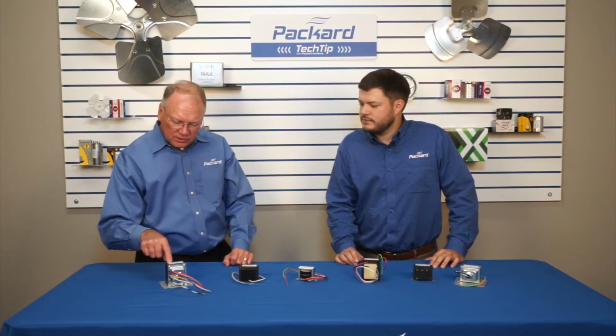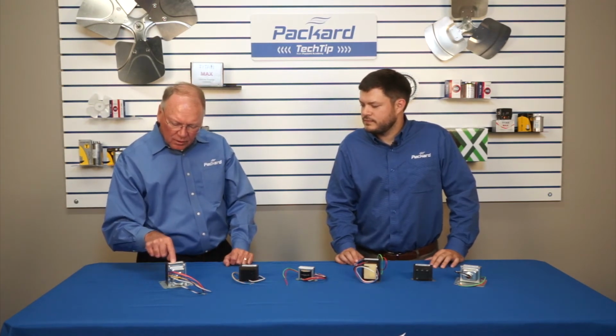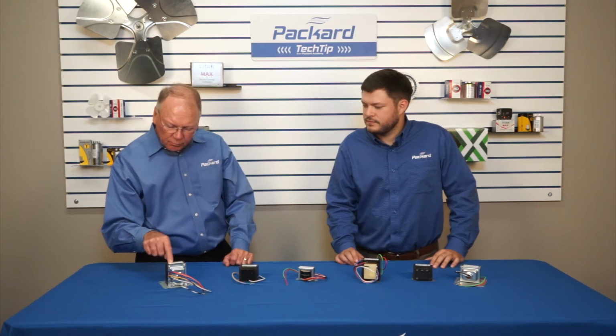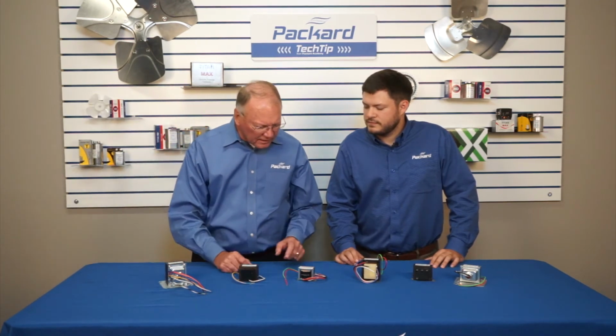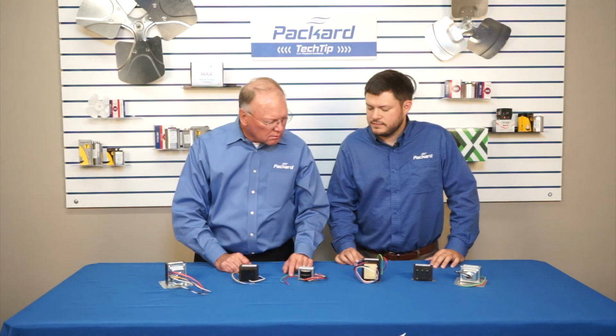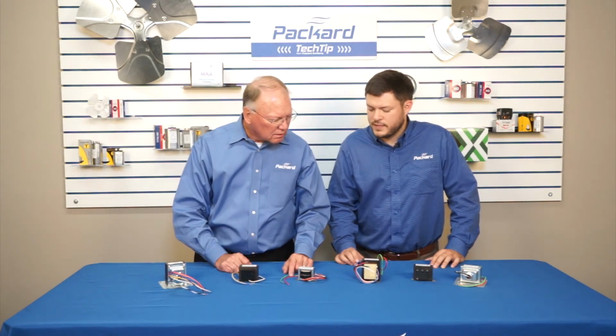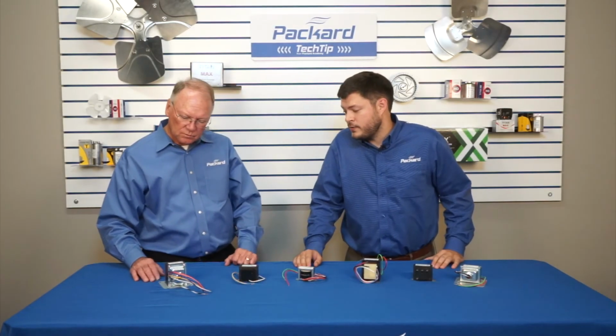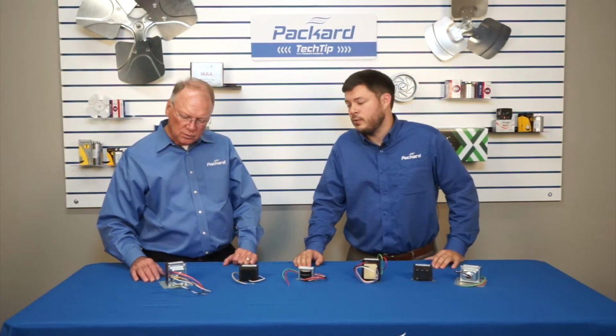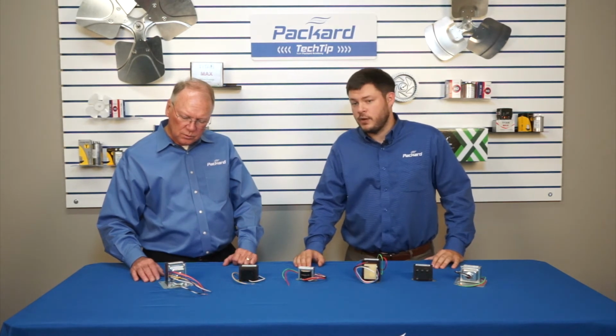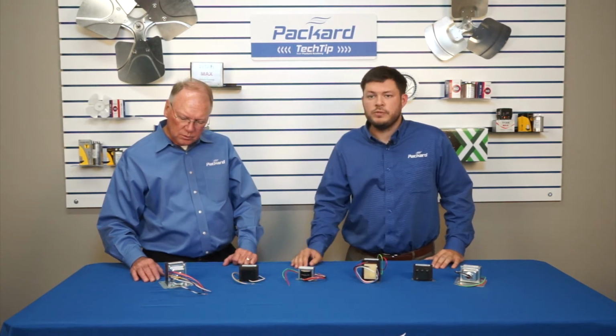So some of these have multiple secondaries. Why is that? To give you additional options on your secondary side as well. This particular one allows for 24 volts or 120 volts on the secondary side based on which pairs of leads you choose.